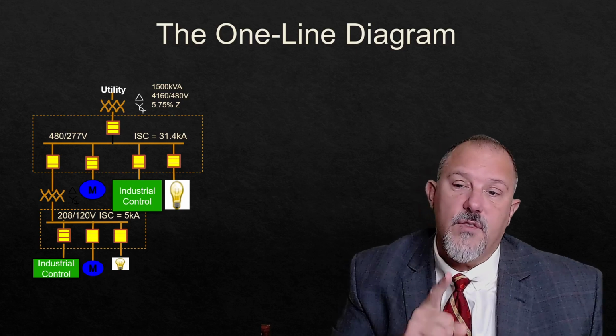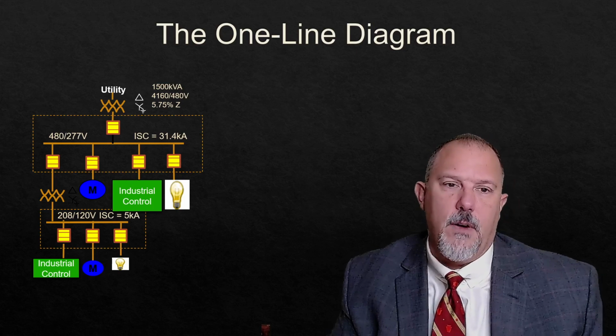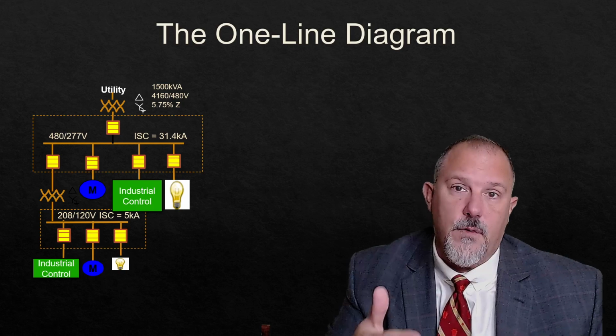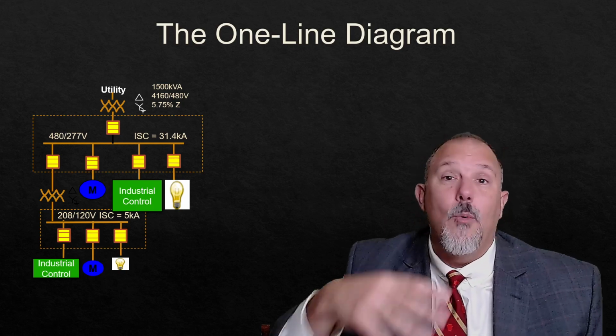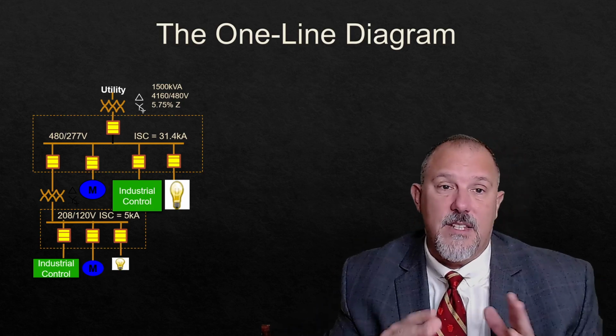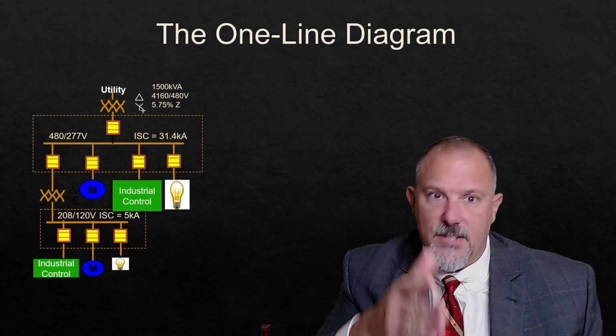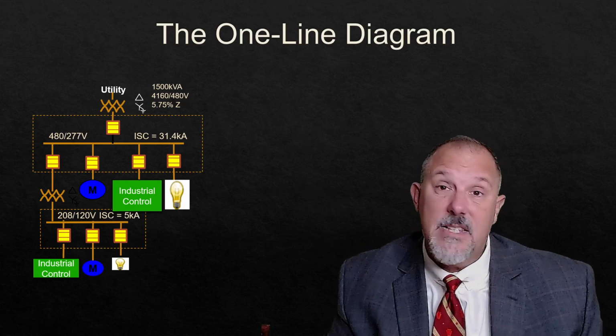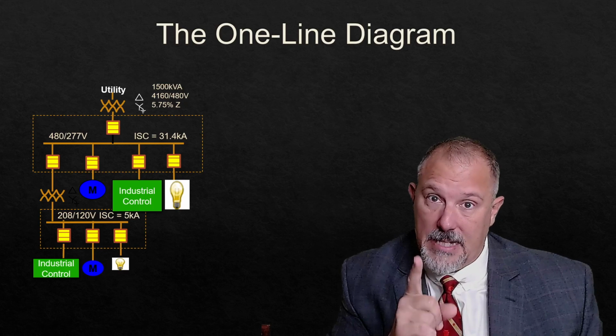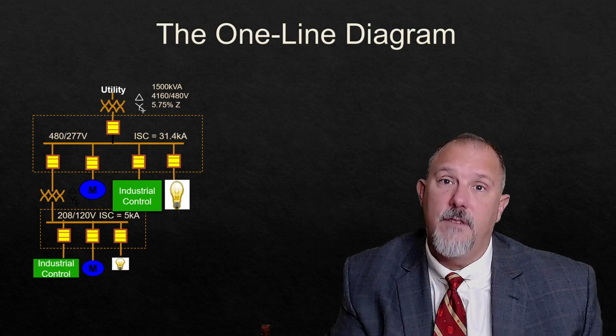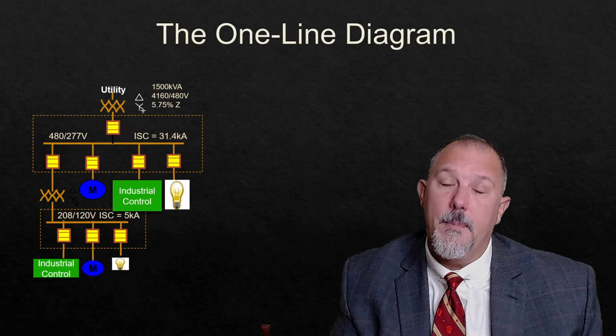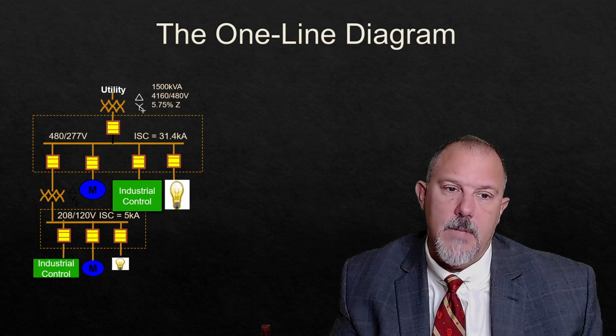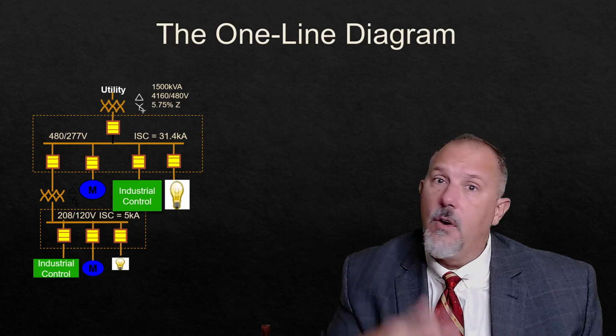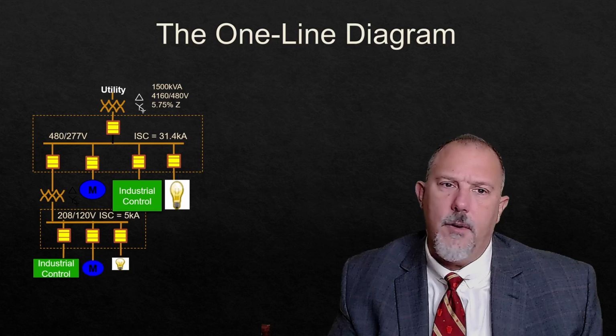Important to know, a transformer does not generate fault current. The utility delivers fault current. The transformer will actually reduce the amount of fault current that it passes on to the system. It's a big hunk of iron. Think about that. The big hunk of reactance for the power distribution system. What else? Voltages, ratios, all that jazz.